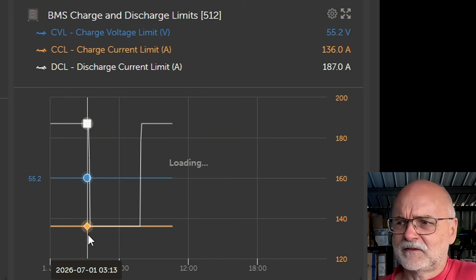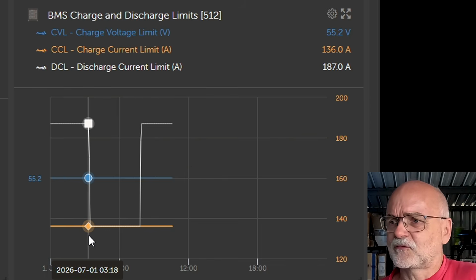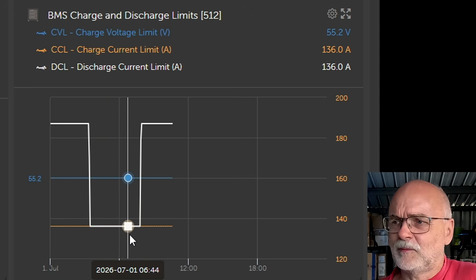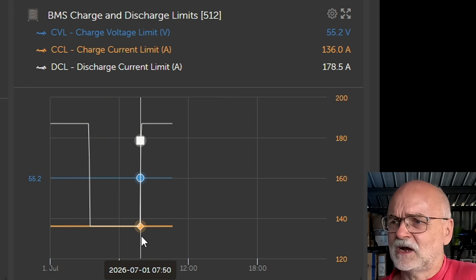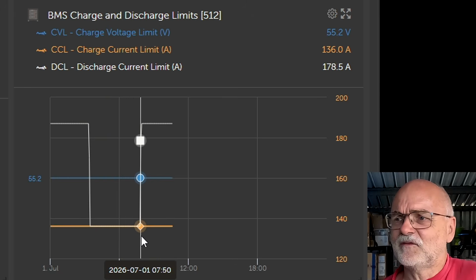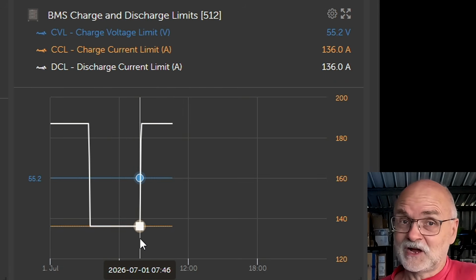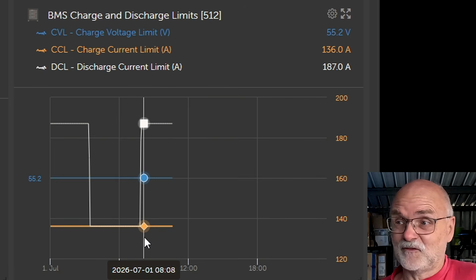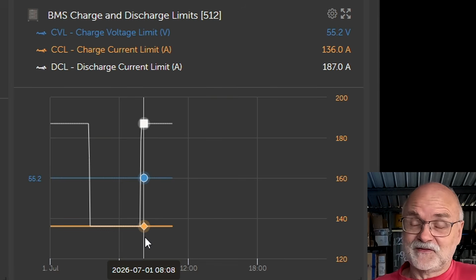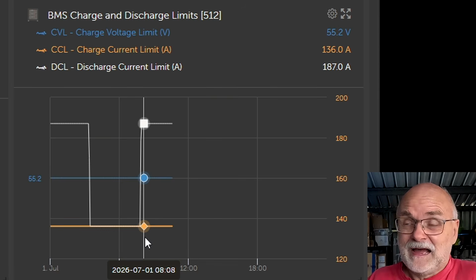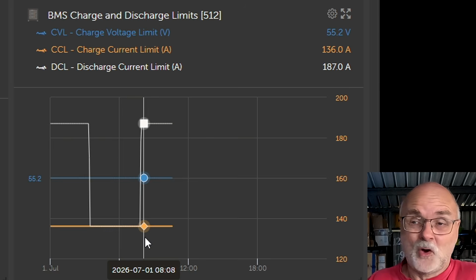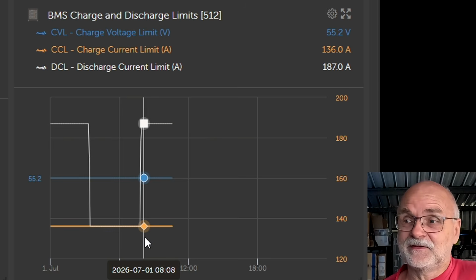And then it was 3:15 in the morning, and then it took a couple of hours to recharge the system. At 7:50 the BMS recovered and said, okay, I'm recharged enough, you can pull the full amps from me again, and the DCL jumped back to 187 amps. So you can see how this regulates if something goes wrong in the middle of the night with one of your BMSs, turns off, over temperature, over current, under voltage protection, like in this case here.